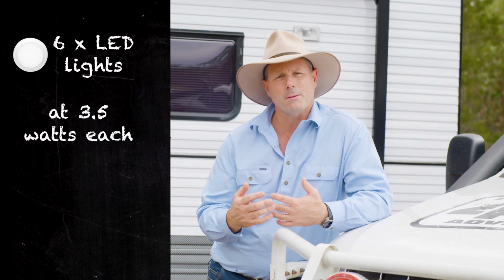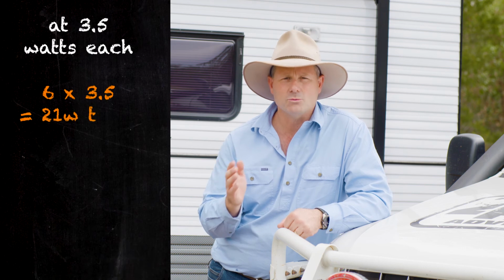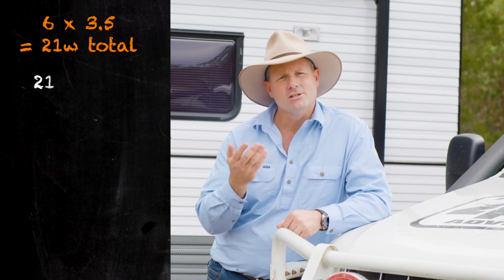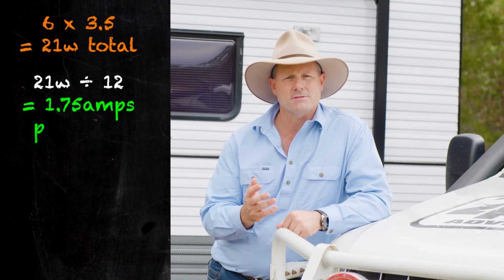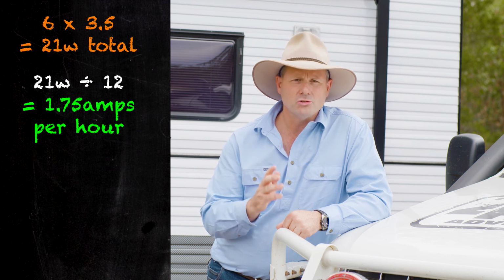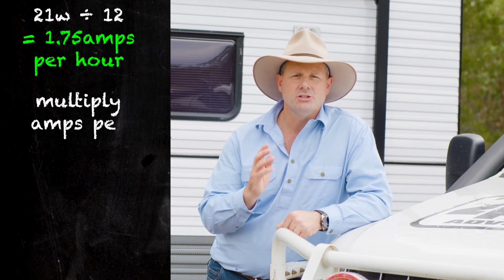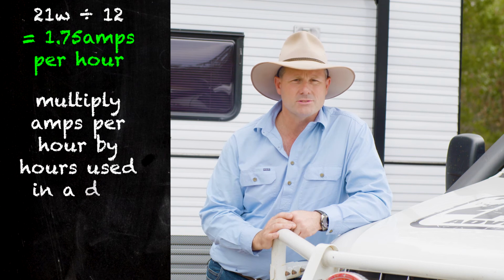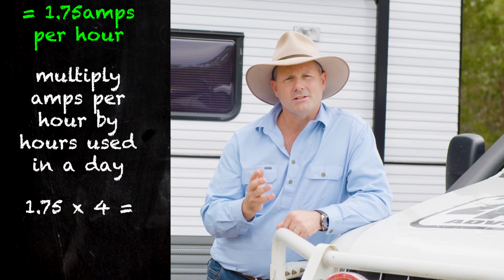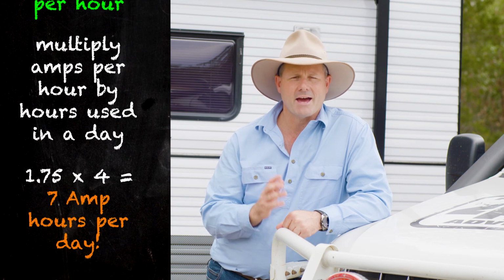First, multiply the number of lights by the rated watts per light. Then divide by 12 volts to get the amps, the light draw. Then multiply this by the number of hours you'll run them. Let's say 4 hours. In this example, you're pulling a total of 7 amp hours out of the battery a day.